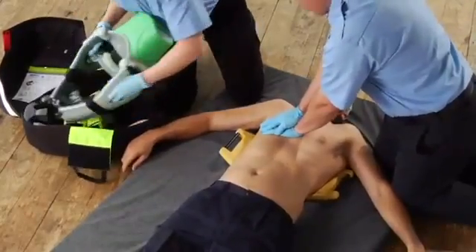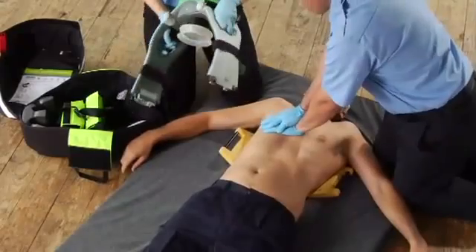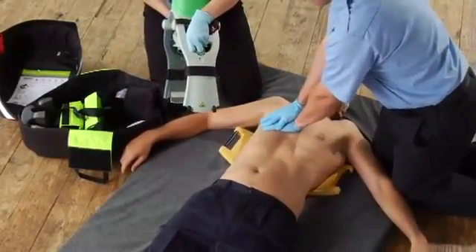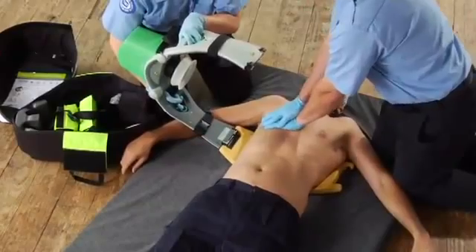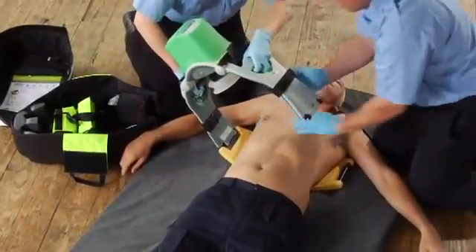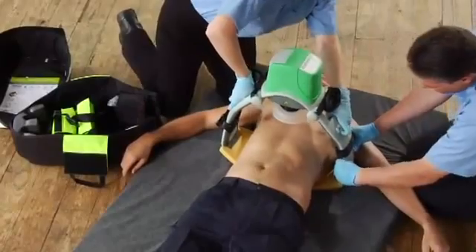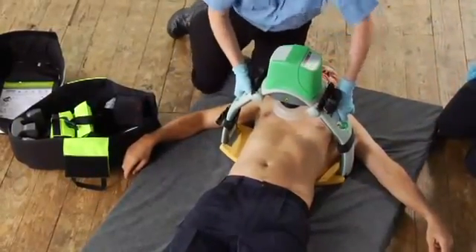Lift the upper part of Lucas out of the bag by the leg handles, and it springs open. Pull up on the release rings until the claw locks open. Now click the closest leg onto the back plate — keep fingers clear. Then stop manual compressions and lock in the other leg. Pull up on both legs to make sure they are locked into the plate. That's very important.